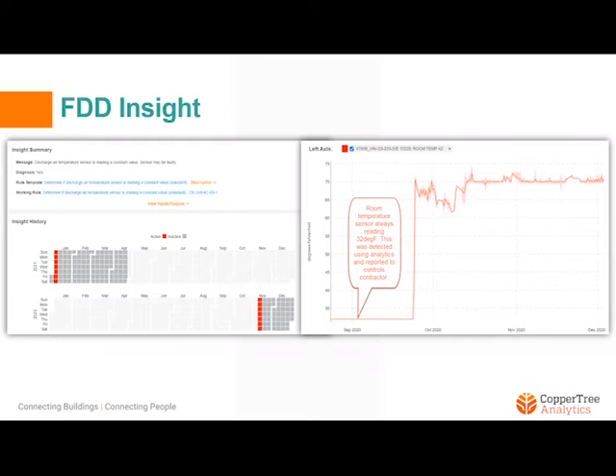You can see that the room temperature sensor for this building, which is based in Seattle, again, this is a real-world practical example, was always reading 32 degrees Fahrenheit. This was detected using the analytics platform and reported to the controls contractor. The controls contractor acted on it, and since then, the issue was fixed. On the right-hand side of that trend log viewer, you are able to see trends, the trend moving up and down, reading different room temperature readings.